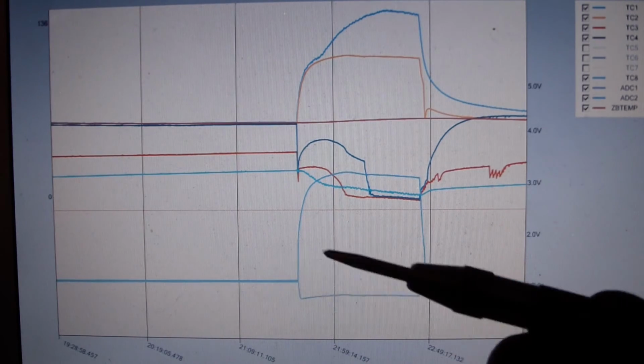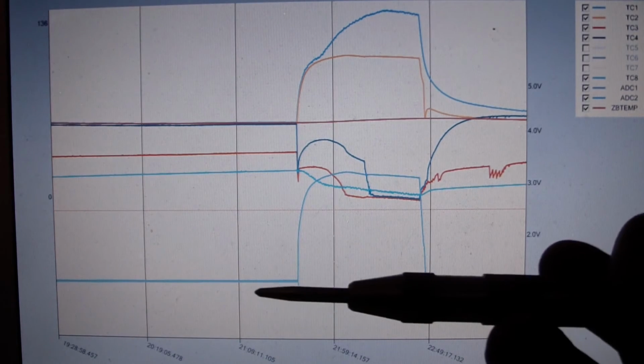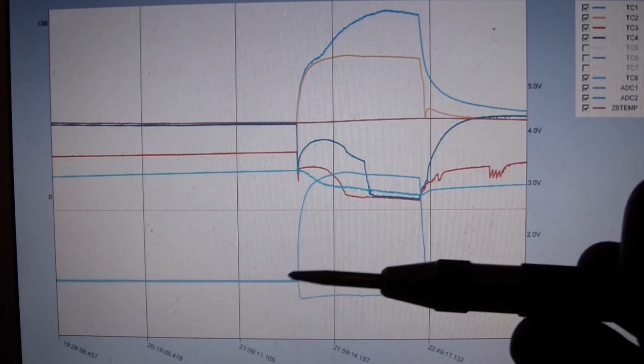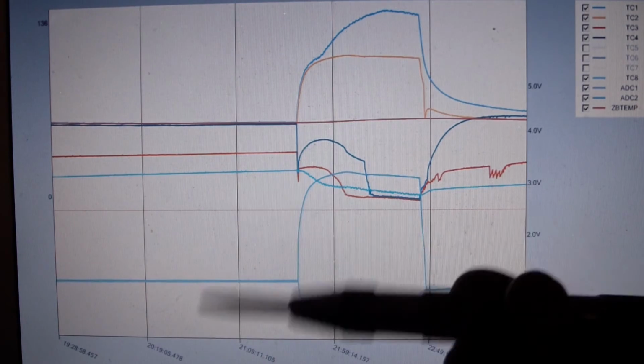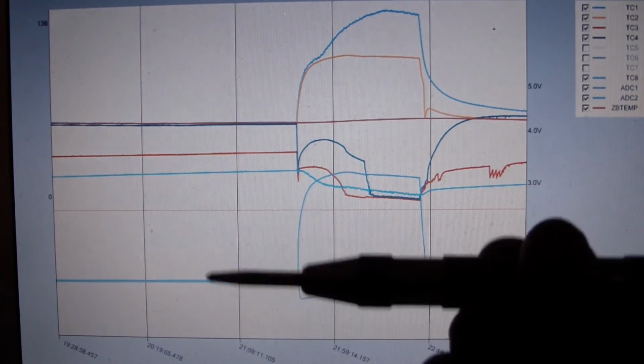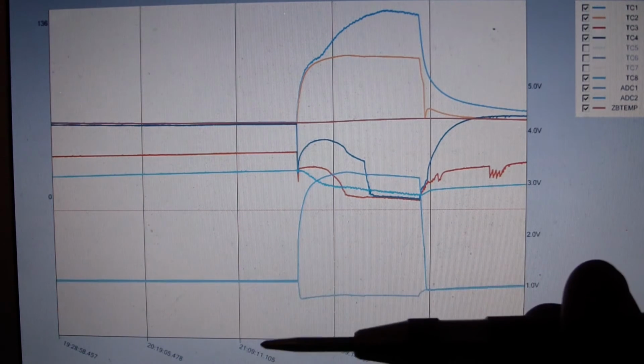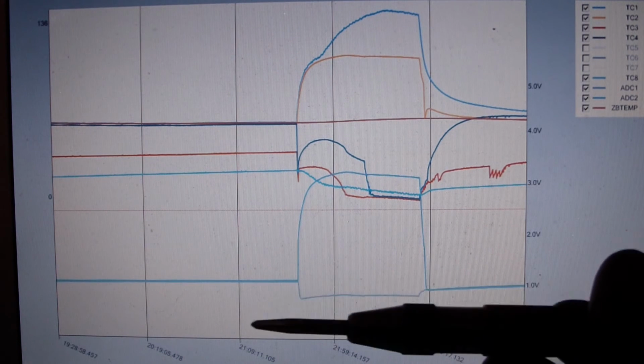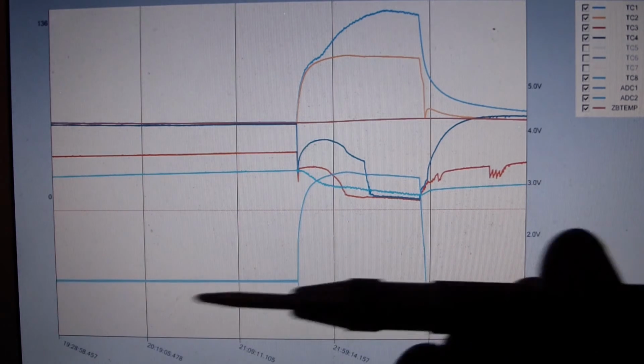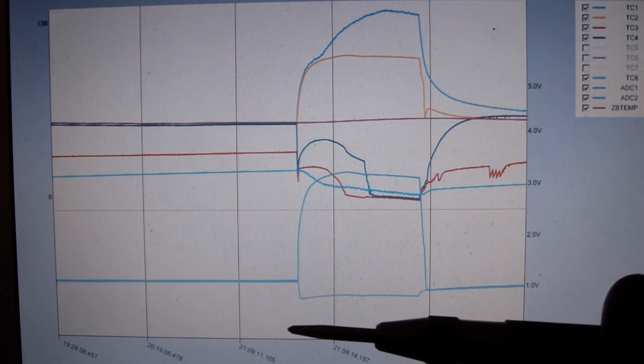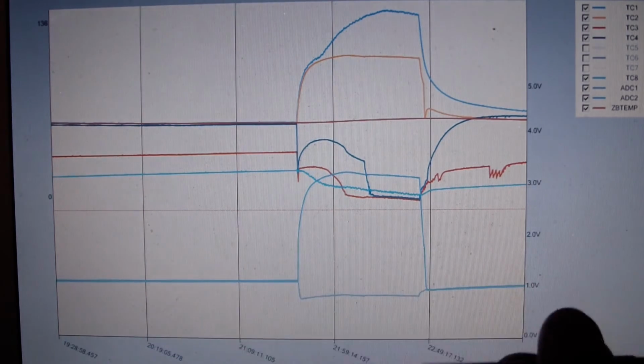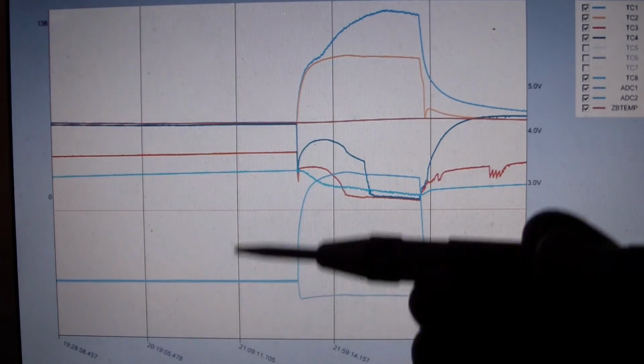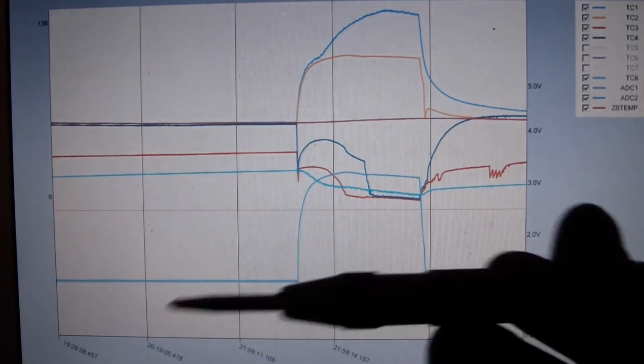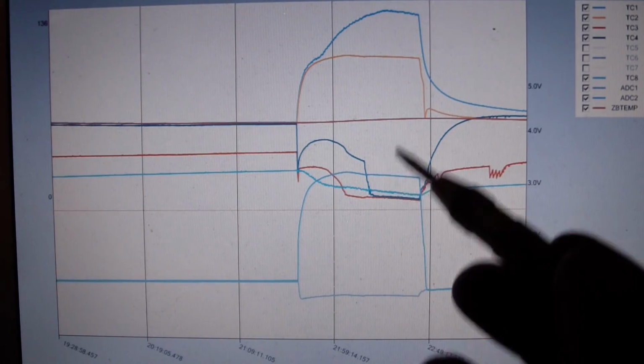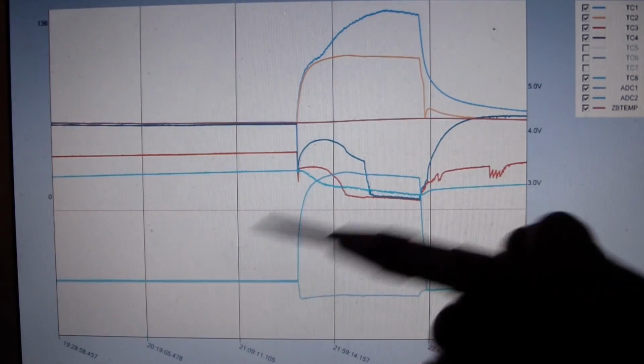In those conditions where that liquid's backing up into the high side, we don't want to starve the evaporator. If the low side liquid is only stored in the coil itself, and a lot of that liquid's backing up into the high side, the coil gets kind of starved, and we end up superheating that gas. We don't really want to do that. We want it to operate in such a way that at all times the evaporator is pretty much well fed. Sometimes it's overfed, in which case liquid can accumulate in the accumulator, and at other times the accumulator can be more or less empty, and the evaporator is still properly fed, and we're getting that saturated vapor, that dense vapor, back to the compressor.